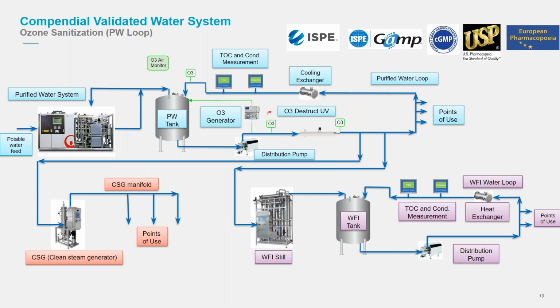The alternative to ozone sanitization is hot water sanitization. So we raise the temperature of the water to above 80 degrees. You hold it for an hour and then cool the system down. And you do these as frequently as required, as the PQ may dictate, whether you do it once a week or bi-weekly. It's all down to your PQ testing and when you set your alert and alarm levels for the critical parameters within that loop.